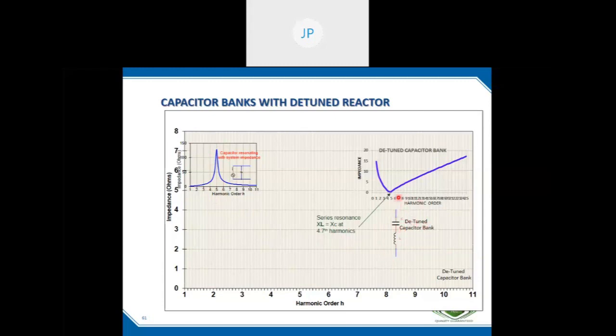So if we tune at 4.7, that means at the 4.7 harmonic frequency the net impedance will be 0. XL minus XC will be 0. This is the impedance characteristic. At 4.7, the impedance is 0. Initially XC was predominant up to this point, and after this, XL is predominant. So from here to here it is capacitive, and from here to here it is inductive.